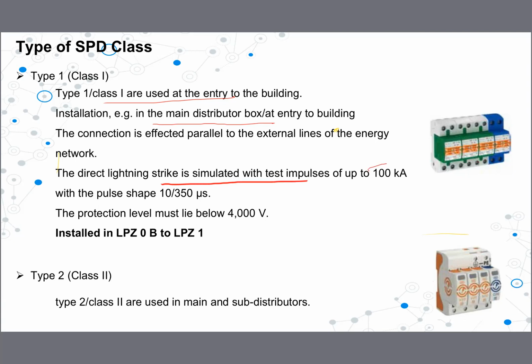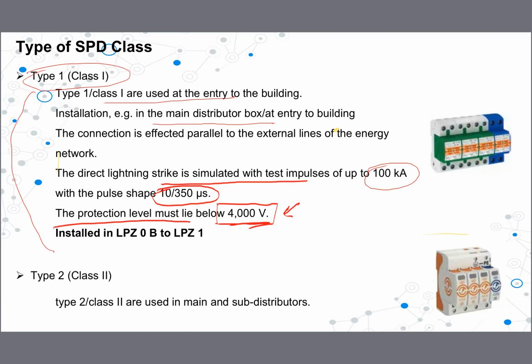Therefore, this is the current value, right? And also this is the test impulse wave type, right? And here it says it should be below 4,000. I'm not going to explain this now. I will explain this below. I have another slide to explain what this voltage level is, right? So remember that we install this class 1 lightning protection device between zone 0B and zone 1, right? That means from the protected area to the building inside.